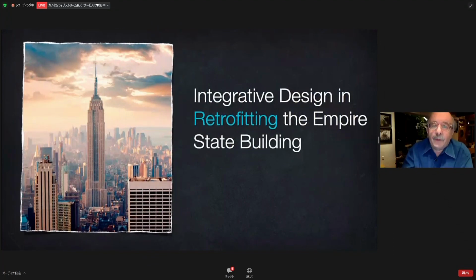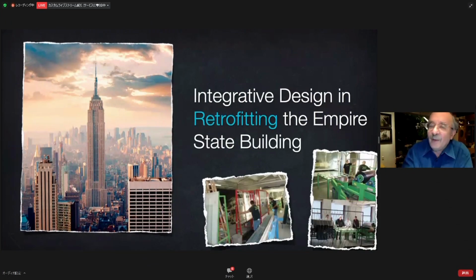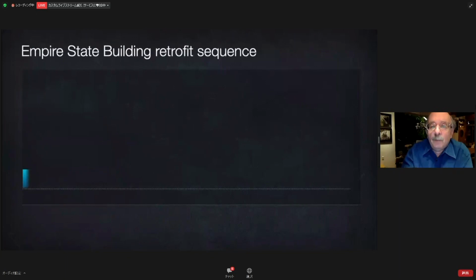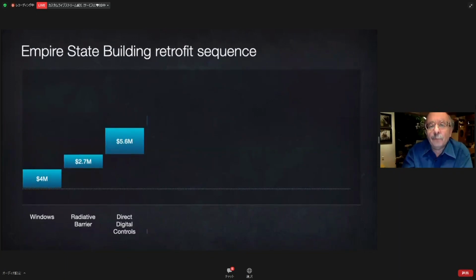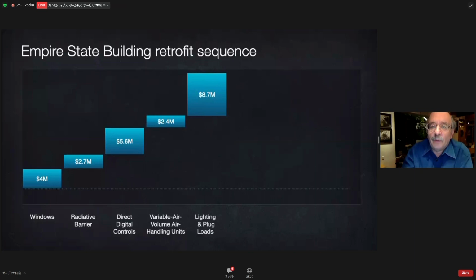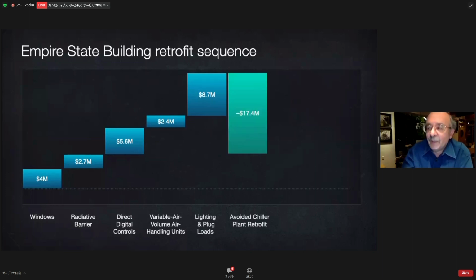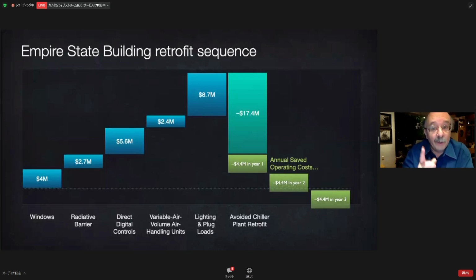That Empire State Building retrofit remanufactured all 6,514 windows on site into super windows that pass light but block heat, plus better lights, office equipment, etc., cutting the maximum cooling load by a third. Renovating smaller chillers instead of adding bigger chillers saved $17 million of capital cost, paying for most of the other improvements and cutting the payback to 3 years, or less than 1 year if we'd counted non-energy benefits to the owner or tenants. A major energy service company had also offered a 3-year payback, but with disintegrated design yielding only one-sixth the savings we got.